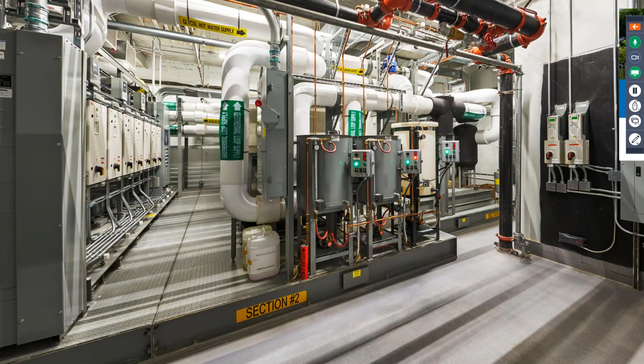First of all, we needed to eliminate the use of the boilers, and we instead installed a geothermal system. There are 30 500-foot deep closed-loop vertical boreholes next to the building, and this is the heat pump chiller skid that connects to the bore field and produces hot water and chilled water to serve the needs of the building.